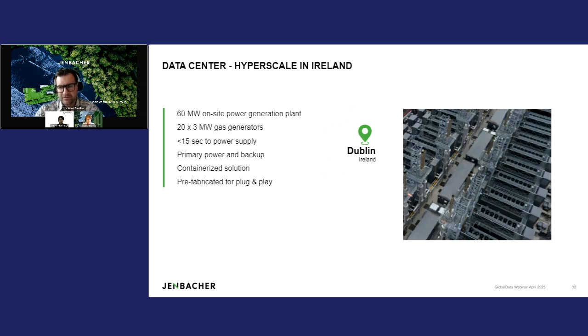Another example is a project in Europe, in Ireland, in one of the data center hubs in Dublin. It's also a 60 megawatt installation, again with 3 megawatt generators each. Power is going to be delivered within 15 seconds. Very interesting here, the client is using our units for both primary power and backup power.